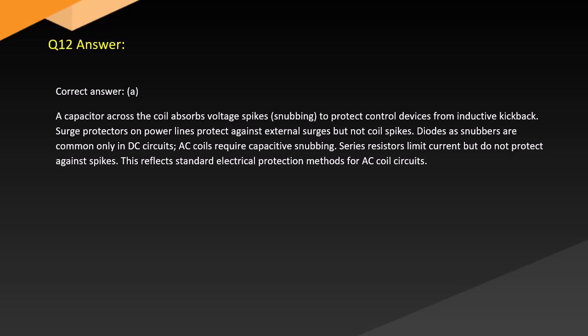Answer. Correct answer: A. A capacitor across the coil absorbs voltage spikes, snubbing, to protect control devices from inductive kickback. Surge protectors on power lines protect against external surges but not coil spikes. Diodes as snubbers are common only in DC circuits, as AC coils require capacitive snubbing. Series resistors limit current but do not protect against spikes. This reflects standard electrical protection methods for AC circuits.